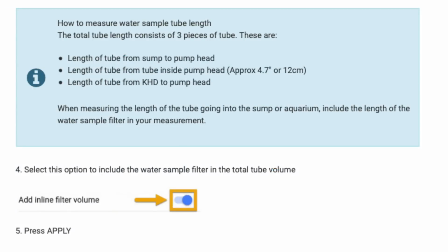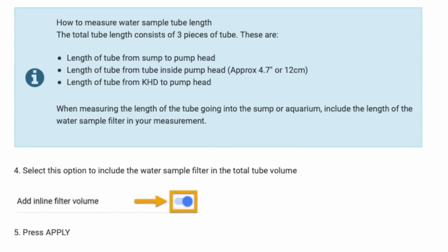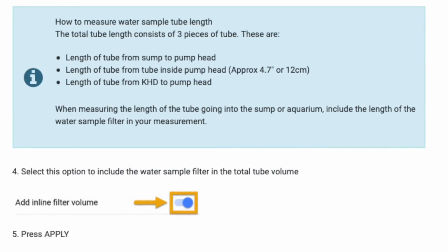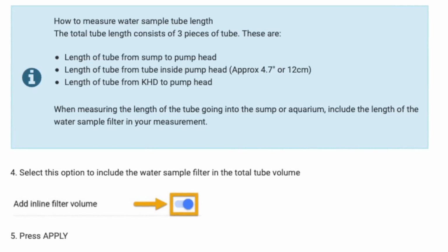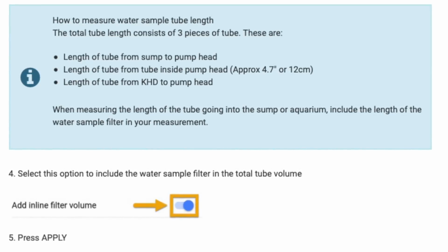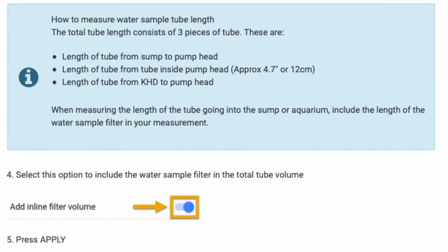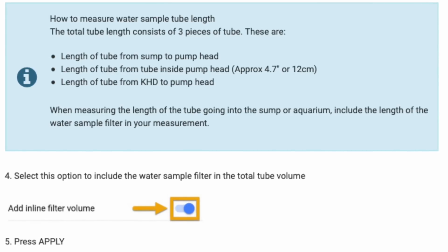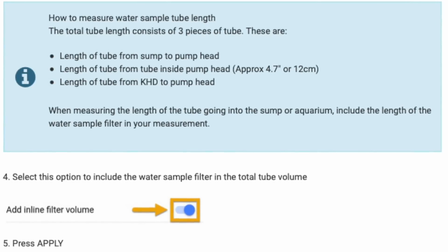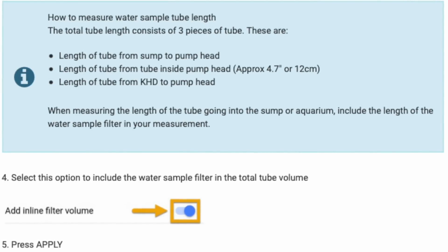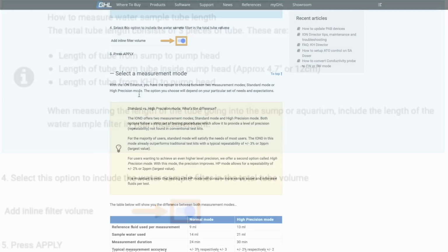Just one other little gotcha I came across here. Not only do you need to measure the length of the tube from the sump to the pump head, include the volume of the filter in that, you also then need to add the length of the tube inside the dosing pump head, and then add the length of the tube from the doser into the Ion Director. Seems like a lot of steps just to work out the volume of that tube.